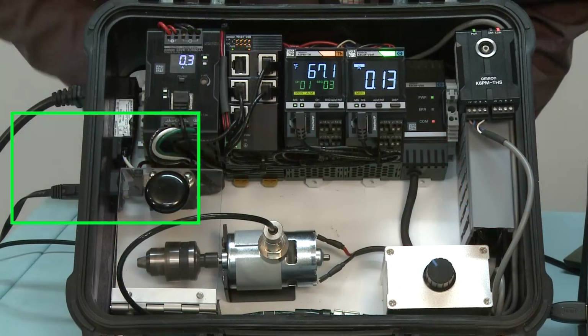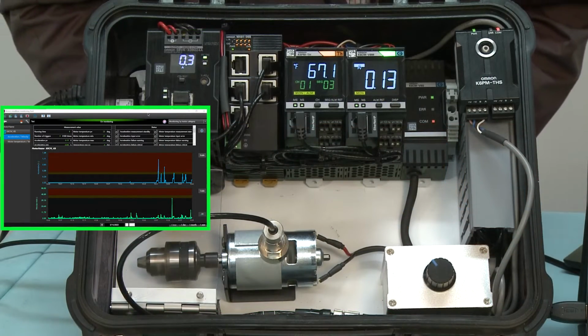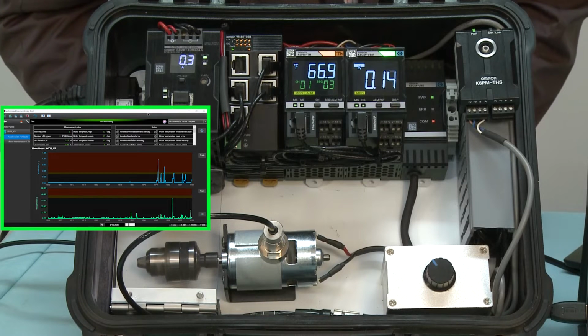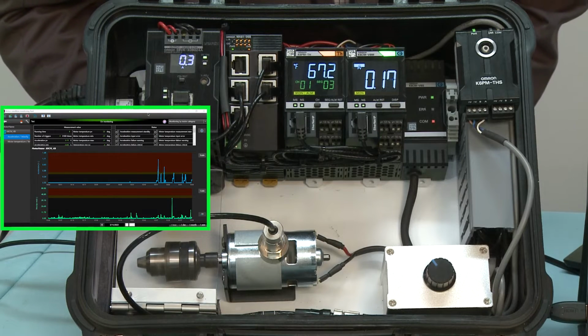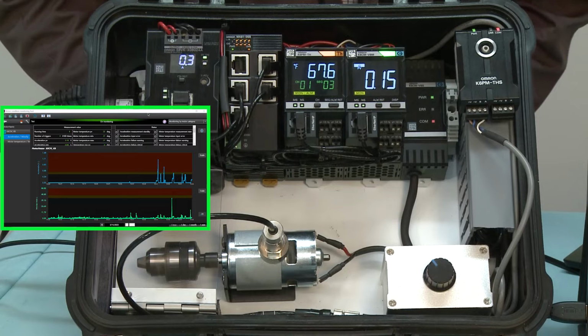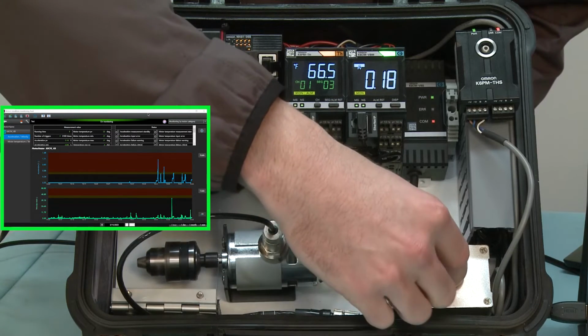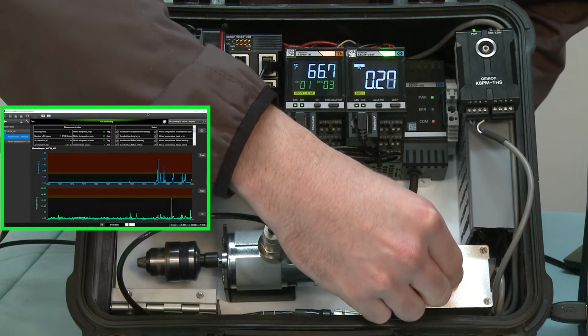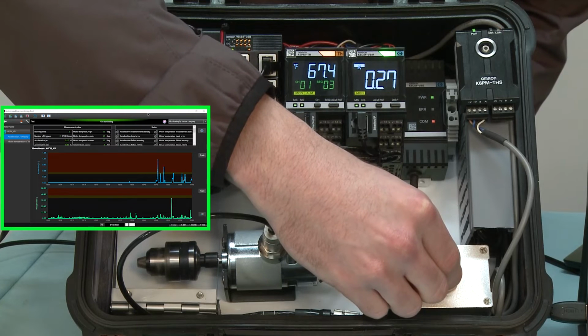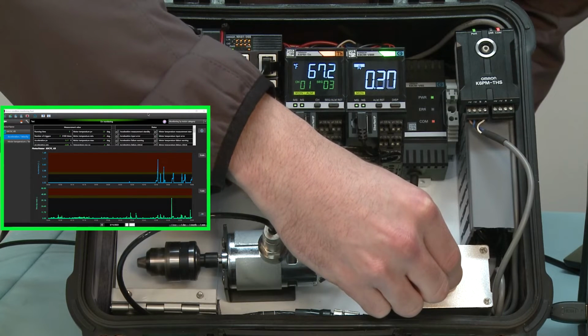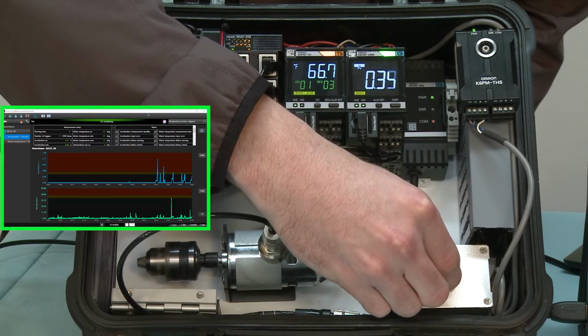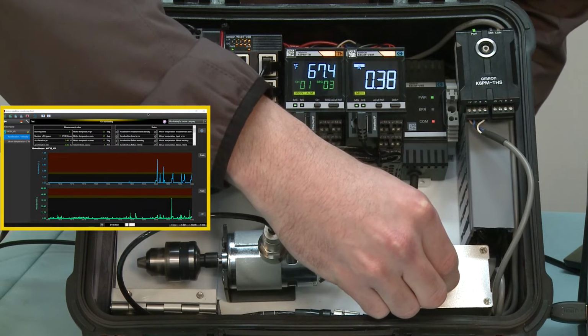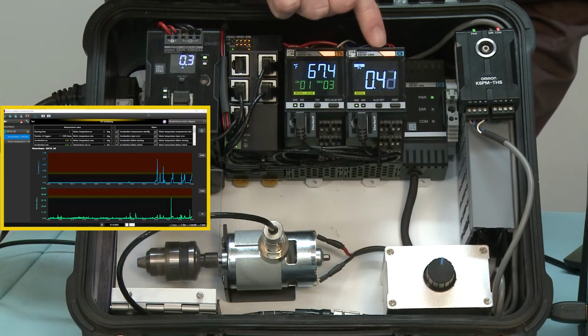So everything's going right, but let's say there's some issue with the motor where it causes some extra vibration that could potentially damage the motor or the systems downstream. I'm going to simulate that now. So I've set a threshold of 0.4 G's to tell me there's something gone wrong. So you see now I have a yellow indication telling me there's a warning, something has gone slightly wrong.